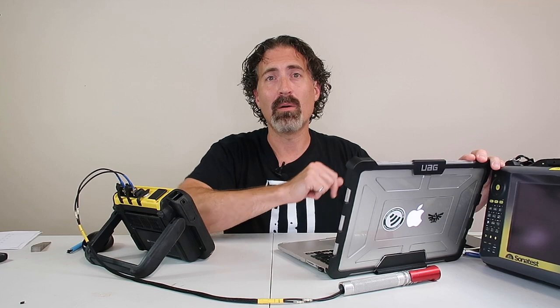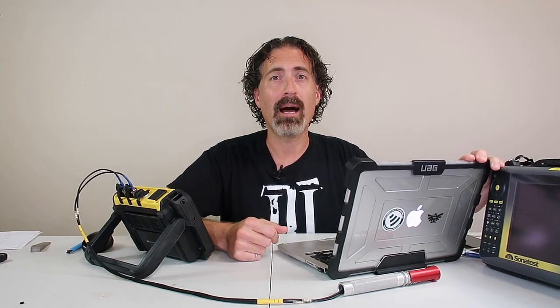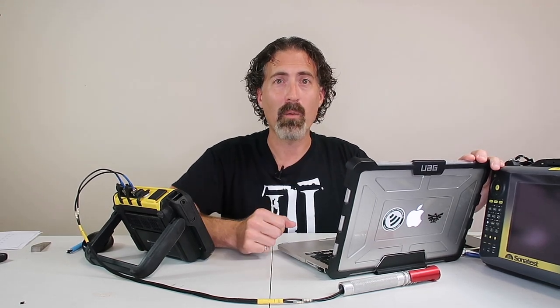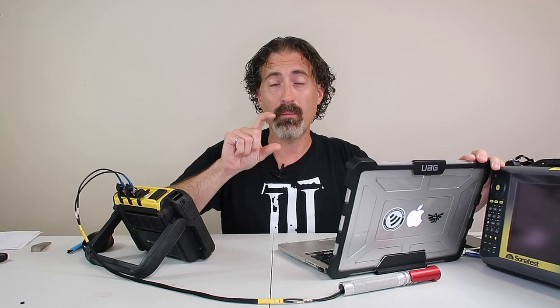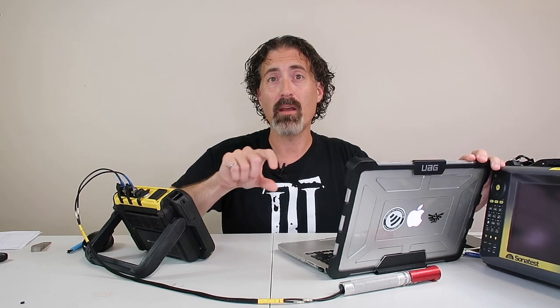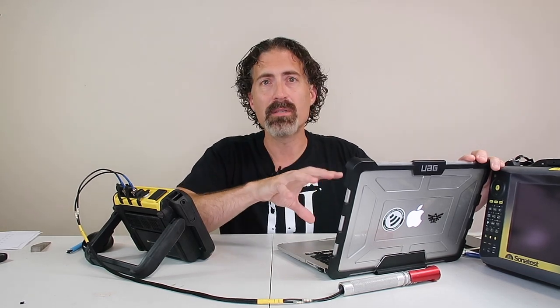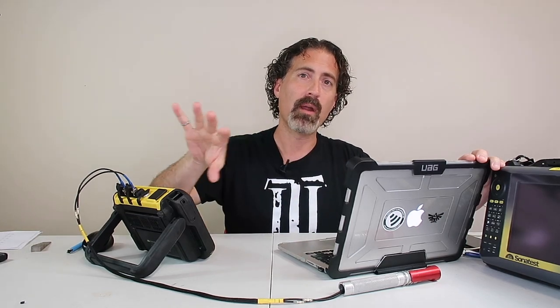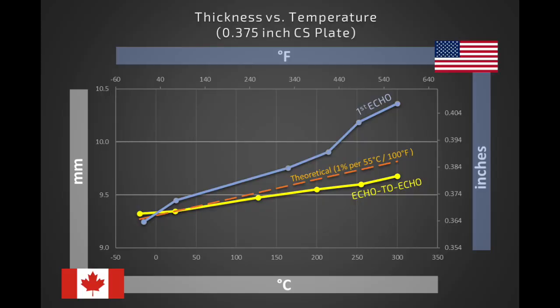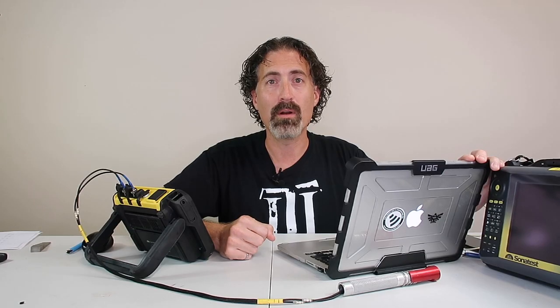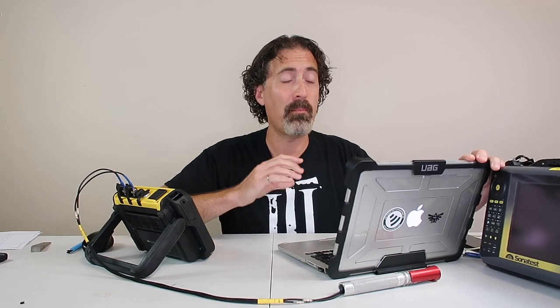Now, a couple days ago, I did the same test, but I did it on the first back wall. So it was the peak of the first peak on the signal, but just using the first back wall, no echo to echo involved. And you can see how completely out of line it is. It completely overestimates the thickness of the steel. Remember, the steel is a 0.375 inch plate, and by the time it got to 300 Celsius, I was reading 0.408, which is a big increase.